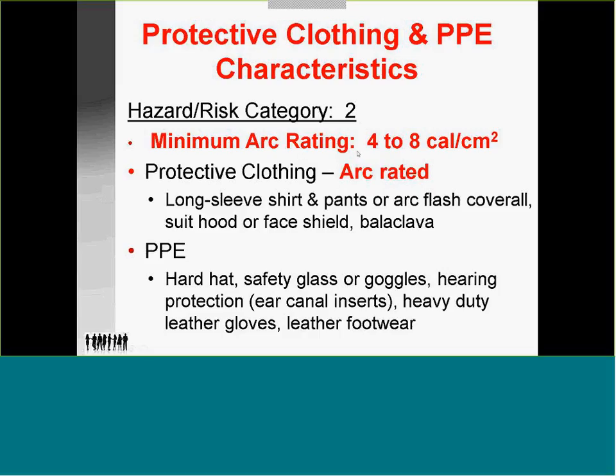Move to a category 2. This is 4 to 8 calories per square centimeter. This requires arc-rated clothing: long sleeve shirt and pants or flash coverall, suit hood, or face shield. But now we bring in the balaclava, and I'll show what that is shortly.